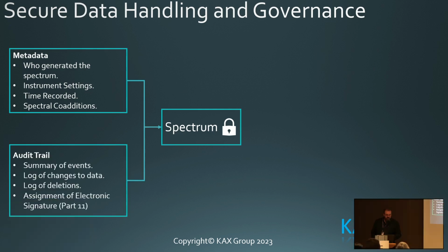The audit trail is a summary of events, a log of changes to the data. Ideally, we should only be changing data that we manually input. Rather, we should never be able to change the spectrum. Log of deletions. Deletions are okay. You get a bad spectrum, something that looks like absolute noise, you can get rid of it from the data set because you can delete that data with justification. If you've got no justification for deletion, then you can't remove it. And we can assign an electronic signature to a deletion, to an acquisition, or to anything else that you do with the data. So the audit trail meets your Part 11 compliance requirements.